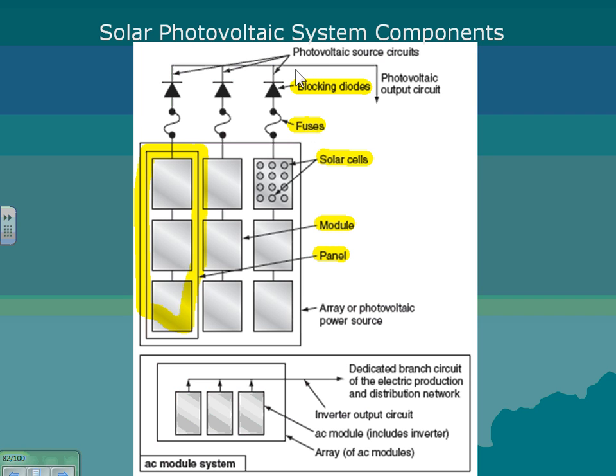Okay, and then we put them right in this area here, guys. They call these the combiner. I'll show you a box. They call them combiners. They combine all these strings in a box with fuses. Just a box full of fuses and a cover, so you can tie these. We have positive and negative out of each one. Negative to negative, positive to positive, except on the positives they put a fuse before they tie in. So that's the panel. They call it the DC system. The top is a DC system.